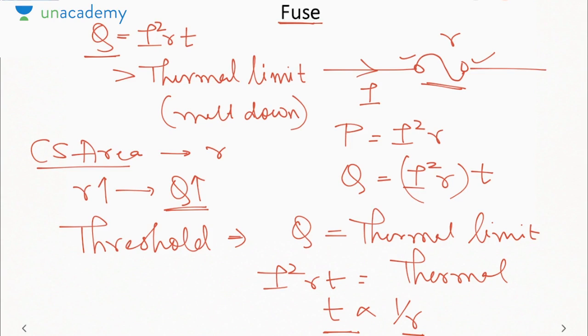a transient type of fault, that is existing for a shorter duration. And usually the fuse meltdown is kind of an undesirable condition. Why? Because this damage is permanent. Once the fuse is melted down, you have to replace the entire fuse. So it must operate only for dangerous faults or only for sustained faults. For faults occurring for a shorter duration, it must not melt down. So lesser operating time or faster operation is not too much desirable in case of a fuse. Okay. So area of cross section is always decided on the basis of resistance.